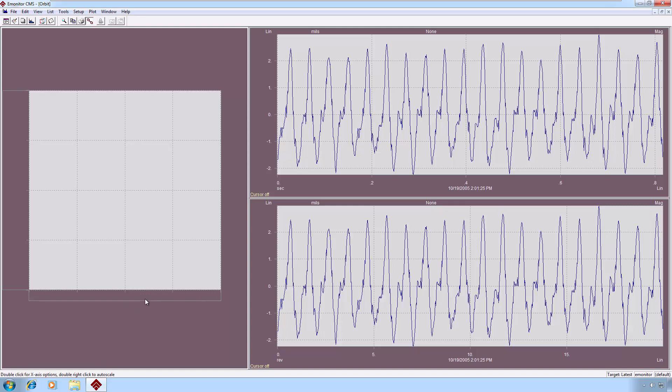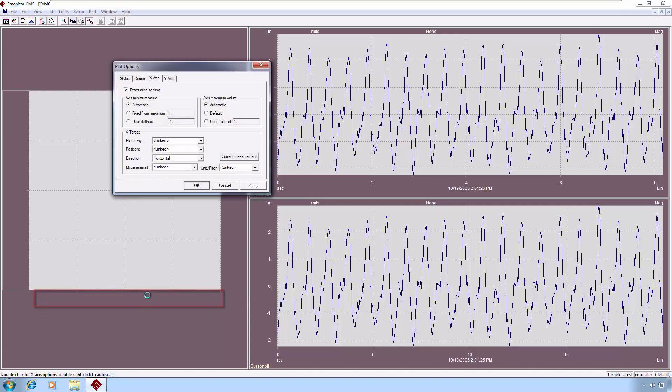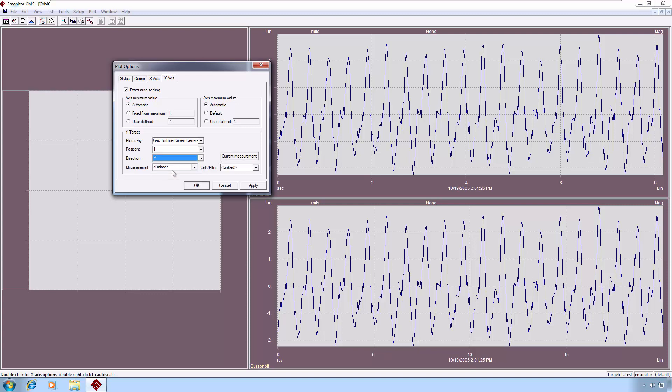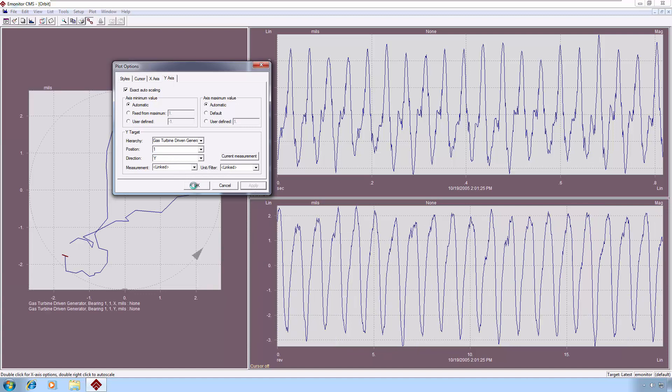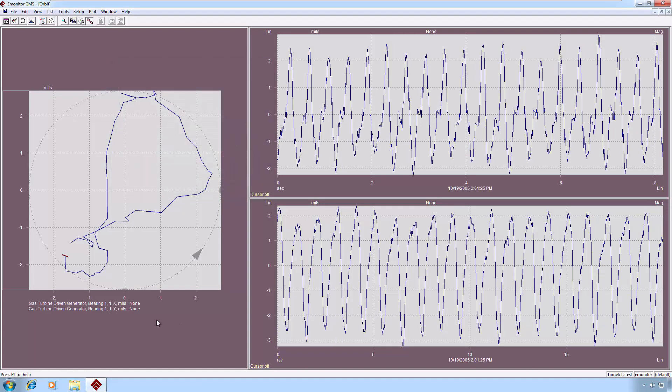So I'm currently cursored on the X axis one, so I will select current measurement, and it'll pre-fill in those position and direction for me. I will then click on the Y axis tab, and again click current measurement. Now since I'm on the X direction, I'll need to change the direction to reflect the actual that I want, which is Y, and I'll apply that. And now you see we will get an orbit plot.